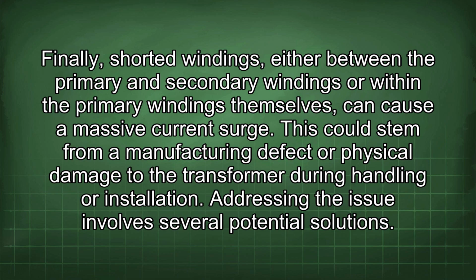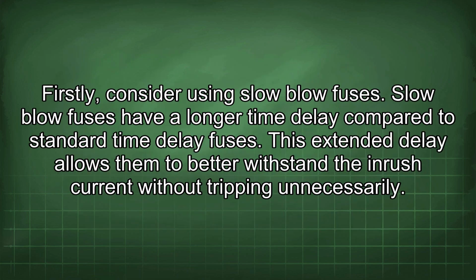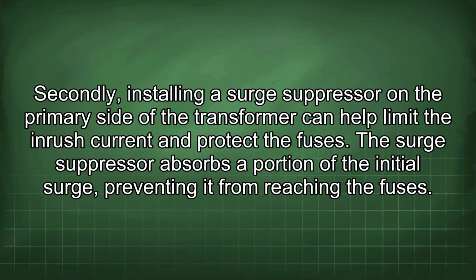Addressing the issue involves several potential solutions. Firstly, consider using slow-blow fuses. Slow-blow fuses have a longer time delay compared to standard time delay fuses. This extended delay allows them to better withstand the inrush current without tripping unnecessarily. Secondly, installing a surge suppressor on the primary side of the transformer can help limit the inrush current and protect the fuses. The surge suppressor absorbs a portion of the initial surge, preventing it from reaching the fuses.